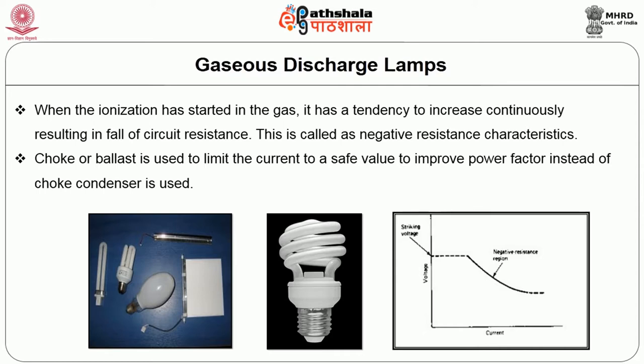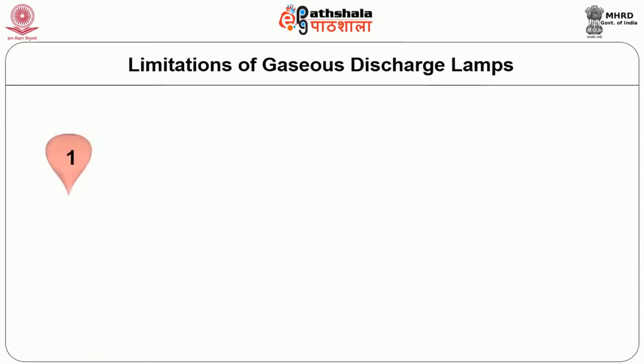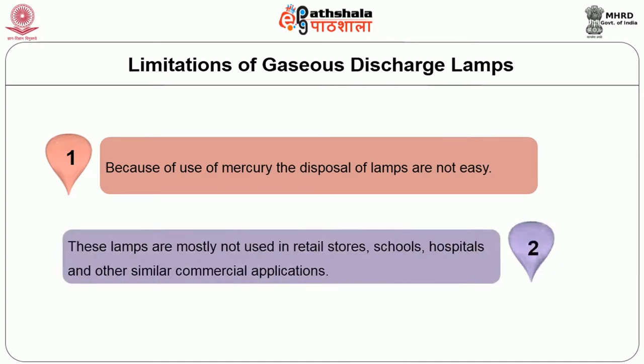Advantages of gaseous discharge lamps: used in outdoor applications, luminous efficiency of 35 to 65 lumens per watt, long bulb life of 24,000 hours. Limitations: because of the use of mercury, disposal of lamps is not easy. These lamps are typically not used in retail stores, schools, hospitals, and other similar commercial applications.